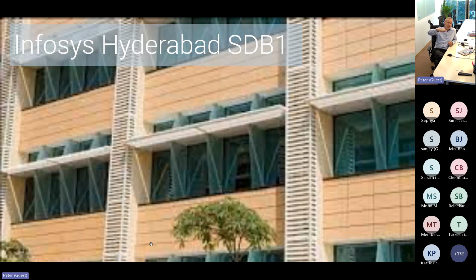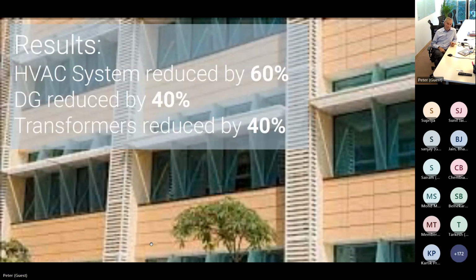You can see this sunshade light shelf, with a daylight window above it that brings daylight into the space and bounces it deep inside. As a consequence, we reduced the size of the HVAC system by 60%, resulting in a much smaller cooling system. The diesel generator system for the whole building was reduced by 40%, and the transformers were also reduced by 40%. These are significant savings on costly systems that use energy throughout the building's life and result in carbon emissions, and that saved money was used to enhance and pay for the better building envelope.